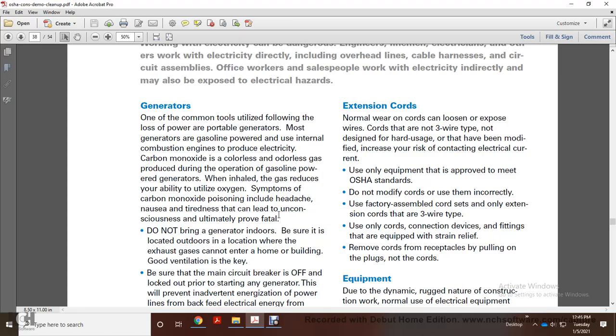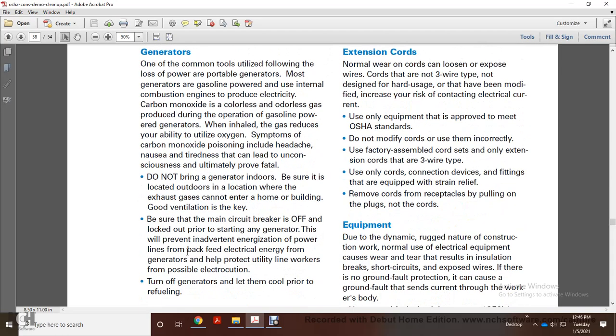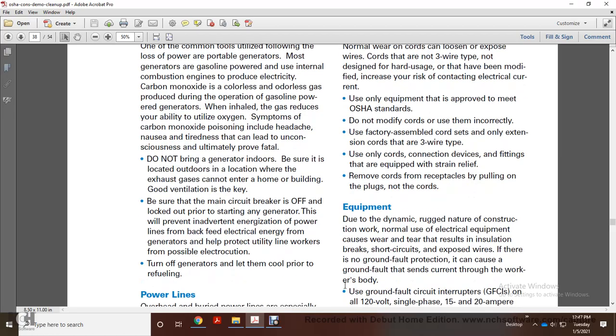Do not bring a generator indoors. Be sure it's located outdoors where the exhaust gases cannot enter the home or the building. Ventilation is key. Be sure the main circuit breaker is off and locked out prior to starting any generator. This prevents inadvertent energization of power lines from back feeding electrical energy from generators. Help protect the utility line workers from possible electrocution. Turn generators off. Let them cool prior to refueling.